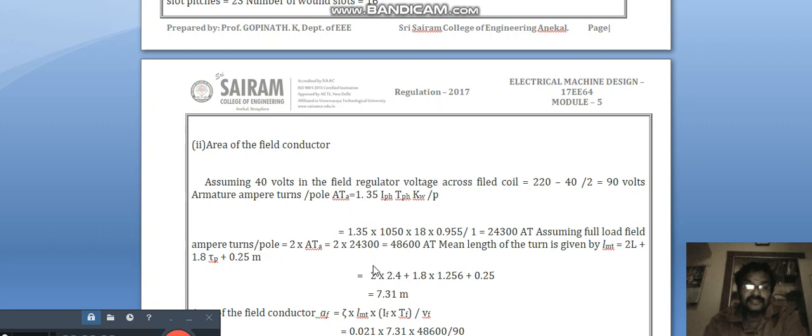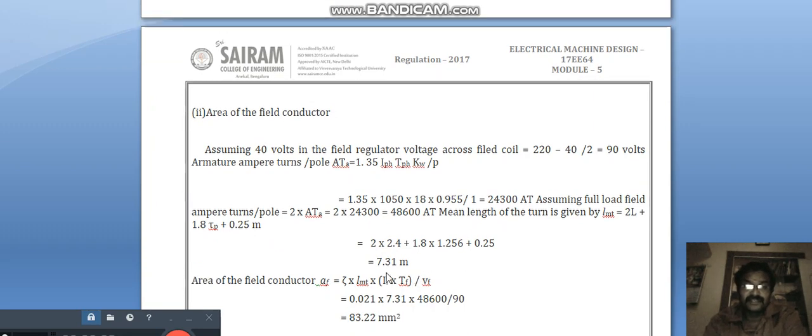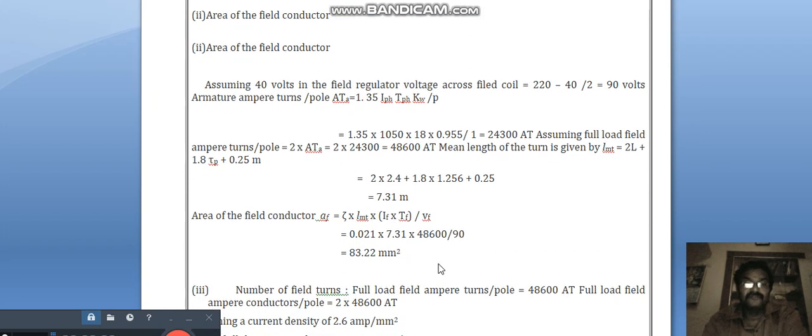Assuming full load field ampere turns per pole is equal to 2 × AT_a. So, 2 into 24,300, we will get 48,600. Mean length of the turn is given by LMT = 2L + 1.8τ_p + 0.25. So, 2 into L 2.4 plus 1.800 divided by width τ_p value 1.256 plus 0.25. So, we will get the value is equal to 7.31 meter.